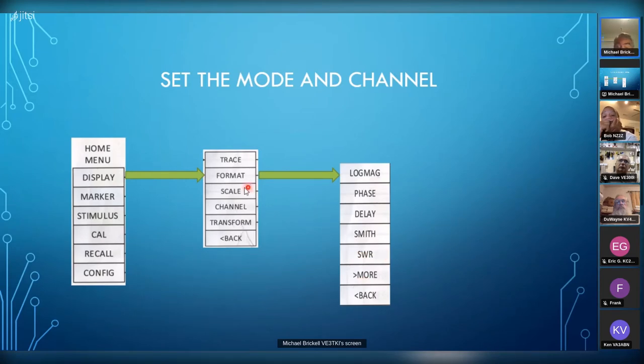You can change the scale of the display, and you can also change the reference level, because when you turn it on, the reference level might not be what you want. When you're looking at transmission, the S21 transmission through, it might be wrong. You might have to adjust the level to see the gain, for example with an amplifier. Otherwise it's off the display.